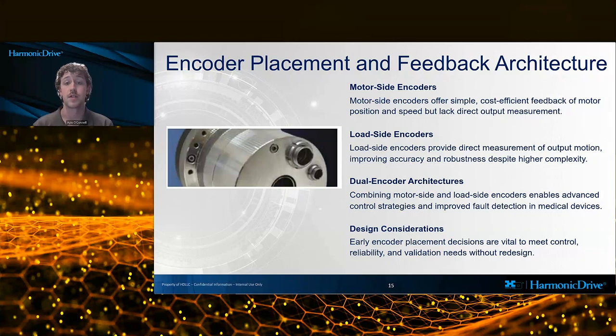Encoder placement is a critical architectural decision in high-precision medical servo systems. You have a few options. Motor side encoders are the simpler and more cost-effective option, providing high-resolution feedback of motor position and speed. But the drawback is they don't measure output motion, and cannot account for gear compliance or deflection under load.